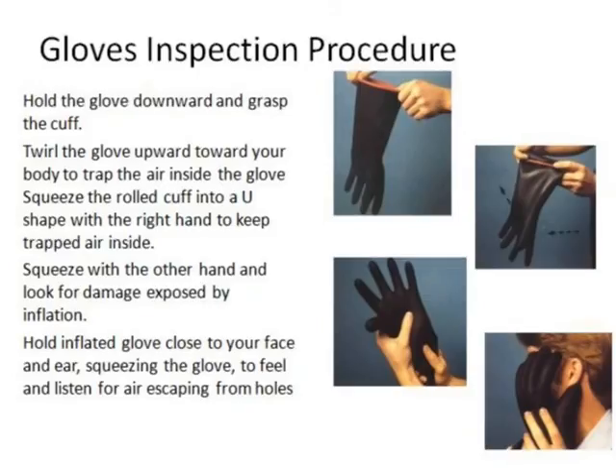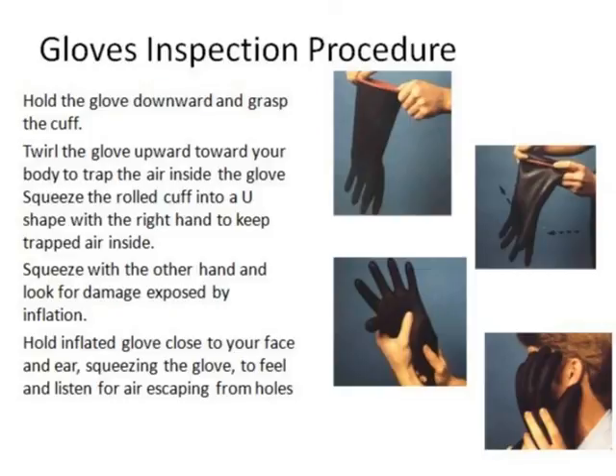For the glove inspection procedure: hold the glove downward, and grab the cuff. Roll the glove upward toward your body to trap air inside. Squeeze the rolled glove into a U-shape with the right hand to keep the trapped air inside. Then squeeze with the other hand and look for damage exposed by inflation. Hold the inflated glove close to your face and ear — it is just like checking a balloon. If there is any problem with your PPEs, this process will help you detect it.